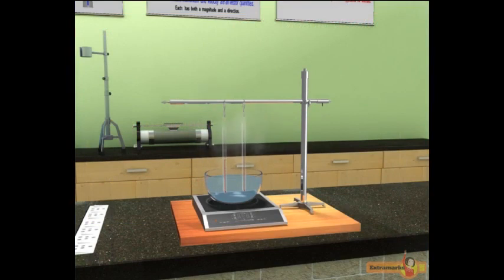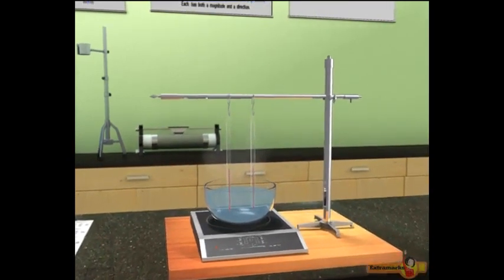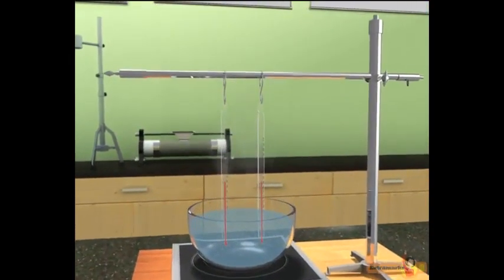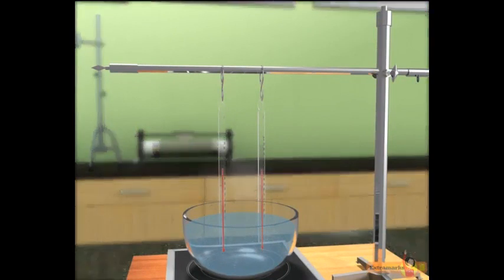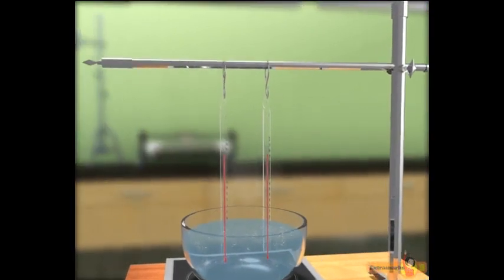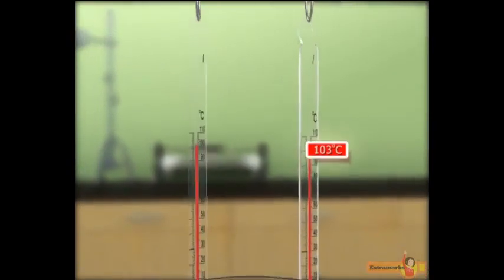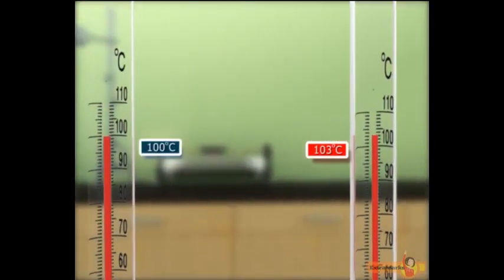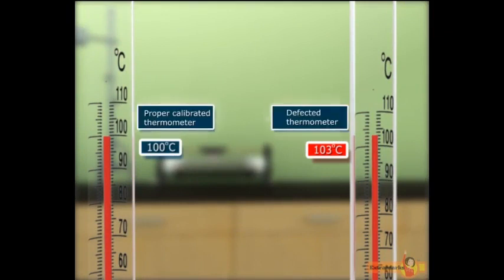Systematic errors occur to the same extent in each one of a series of measurements. That means it tends to be in one direction, either positive or negative. For example, a thermometer with inadequate calibration may read the boiling temperature of water as 103 degrees Celsius instead of 100 degrees Celsius at STP, and will give an incorrect reading to the same extent consistently while measuring. This means it tends to be in one direction.